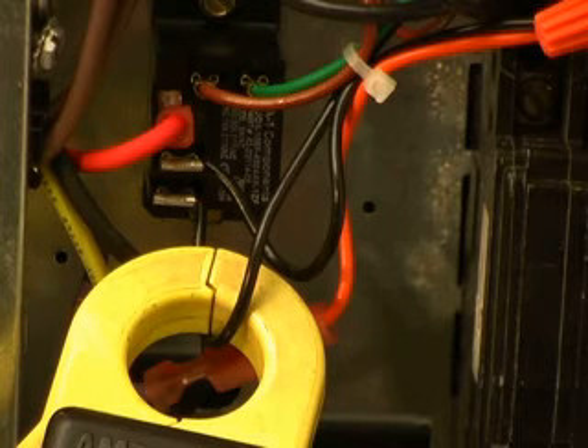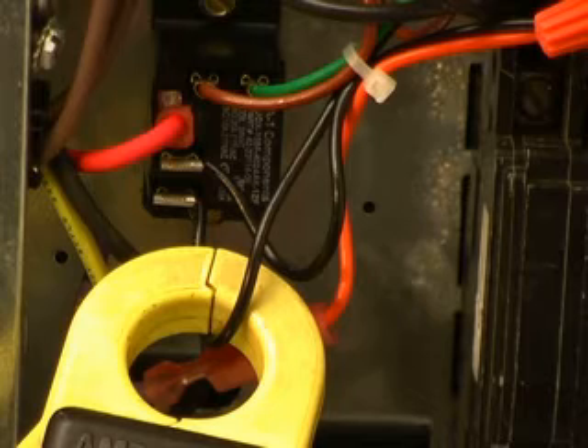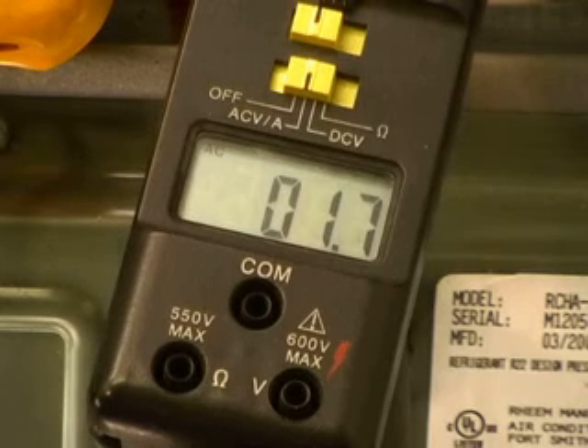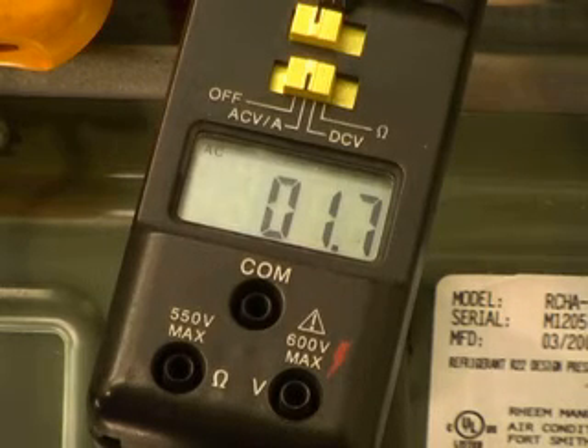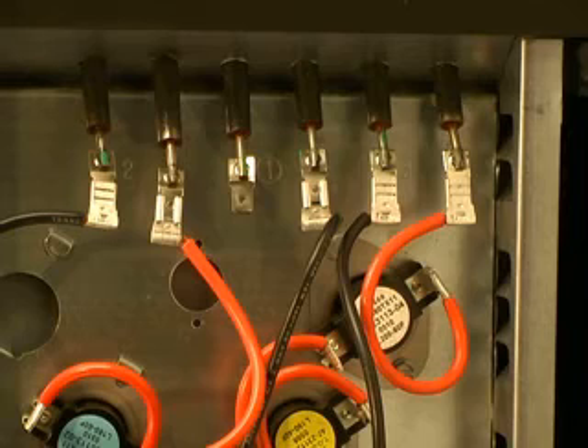normally closed set of contacts. So it's closed when the relay's not energized. And if we look at the amp meter, we see that's where our current's coming from, through that normally closed side. So that tells us it's got to be coming off one of the sequencers. And at that point, the quickest solution is just to go to each one of the leads coming off the strip heat and see which one's pulling current.